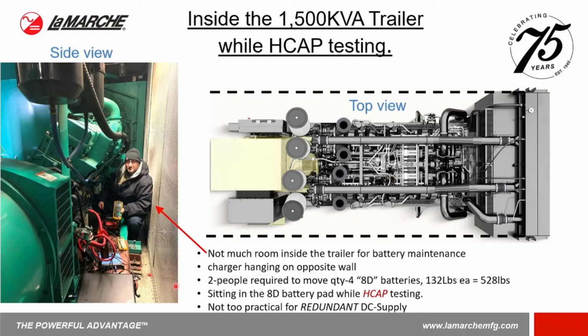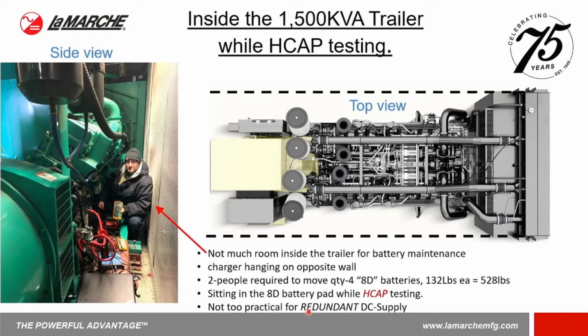So there's not much room for multiple people to be changing out lead acid batteries, anything like that. And two people would be required to move a single 8D battery because they're in the vicinity of 125 to 132 pounds. So where I'm at in this picture, I'm actually sitting on the battery pad while doing HCAP testing. So in a small cramped area like this, there's not too much room for a truly redundant DC supply system.